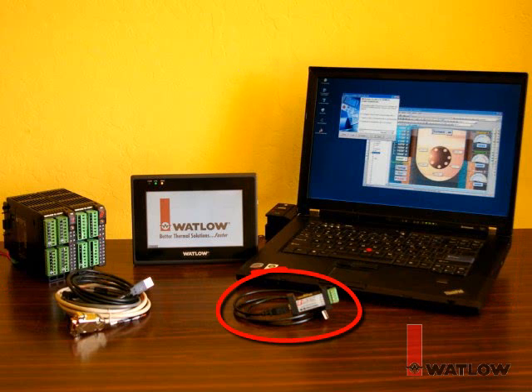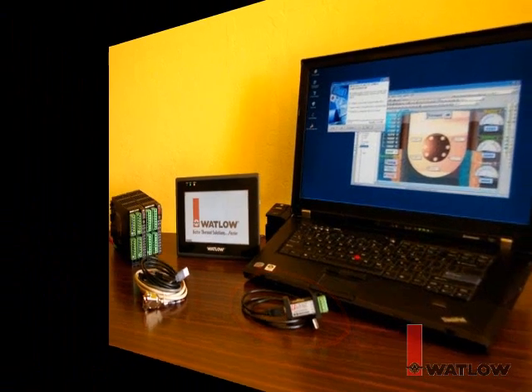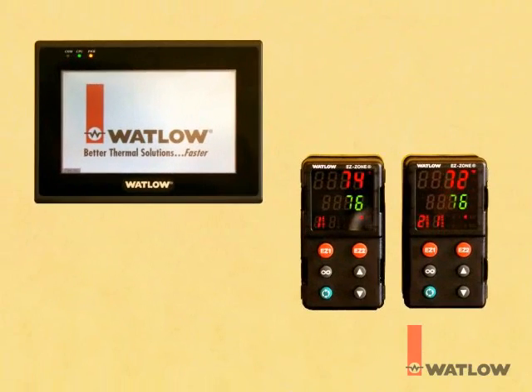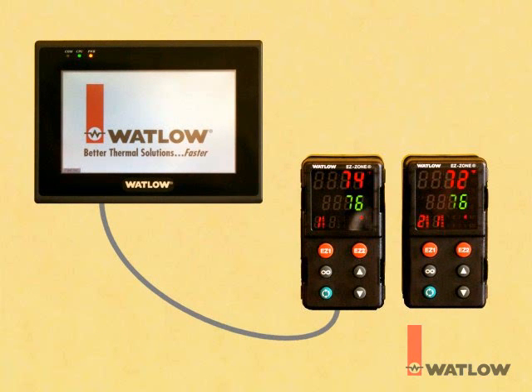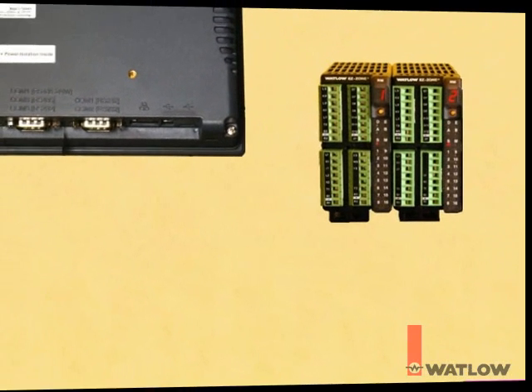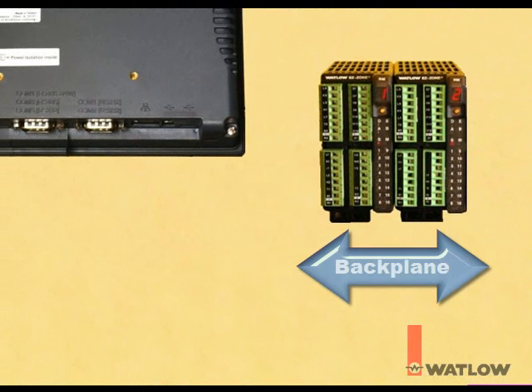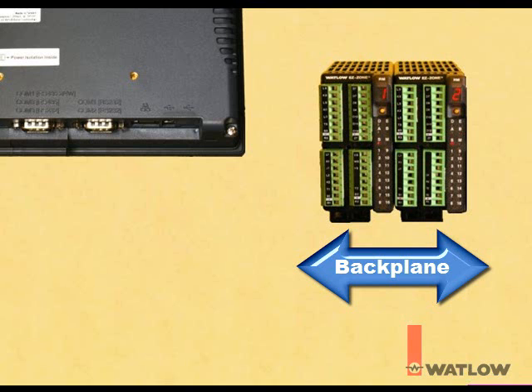...and a USB to 485 converter and communications cables. A Silver Series OIT may be connected directly to one EZ-ZONE controller using the cable available from Watlow, and from there to additional controllers daisy-chaining them together with shielded twisted pair communications cable. When connecting to an EZ-ZONE RM system that consists of more than one module connected together at their backplane connectors, connect the 485 network to only one module. The backplane connects the network to the other modules for you.